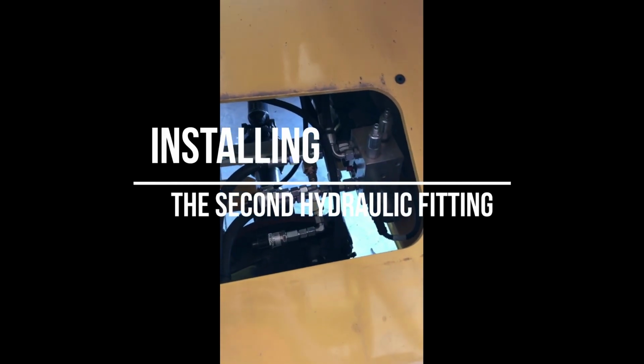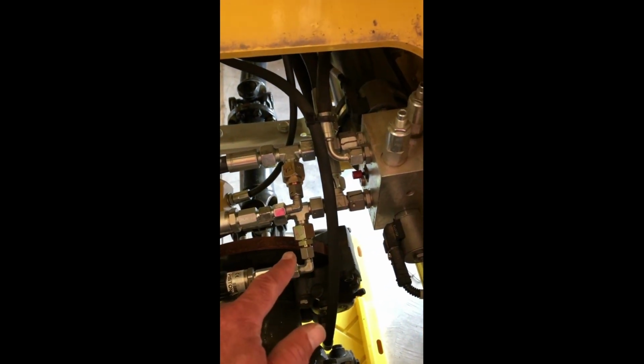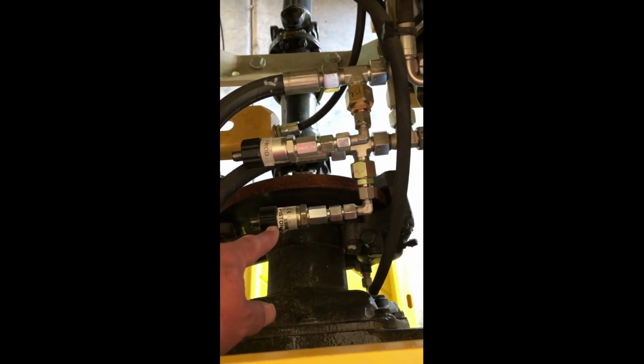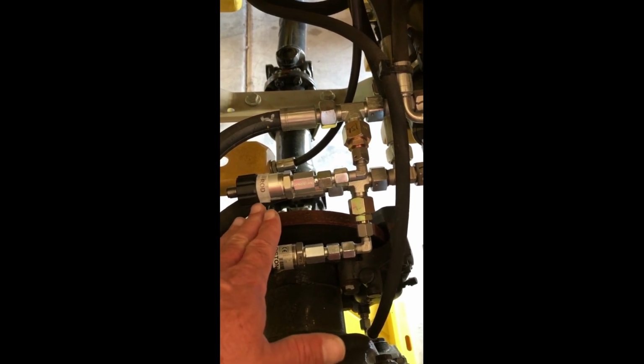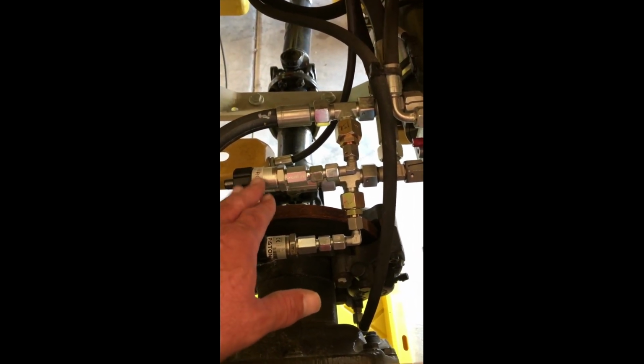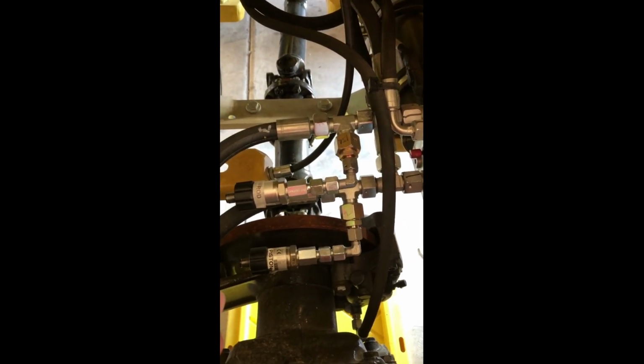Here is a shot of the pressure transducers. I traced the lines from the one cylinder on this machine down to where it comes out of the valve here, and installed T's. You can see this one's labeled piston, so that will go to the back end of the lift cylinder. And the other one here marked rod, that goes up to the rod end out here. Also, try to install your sensors where the end of the sensor is kind of running uphill, that will allow any air that might be trapped in the sensor to hopefully escape out and go back through the system and out into the tank.